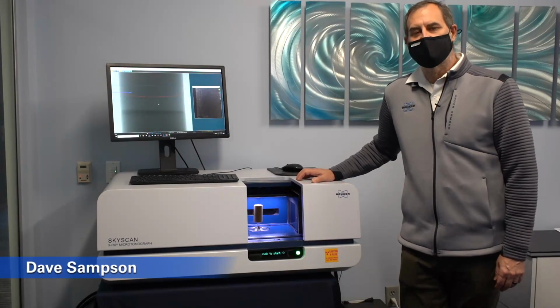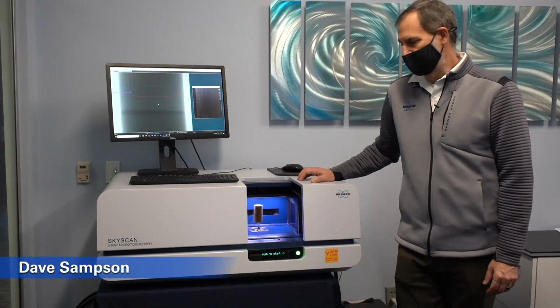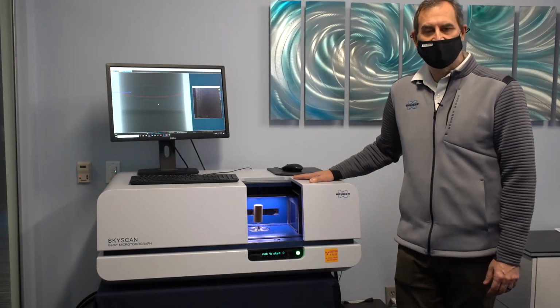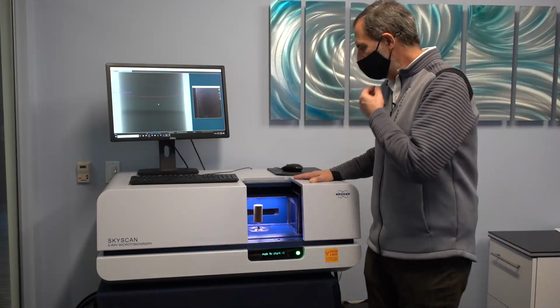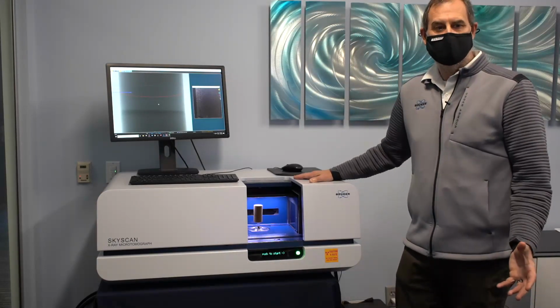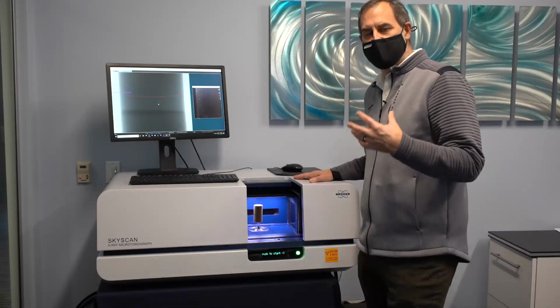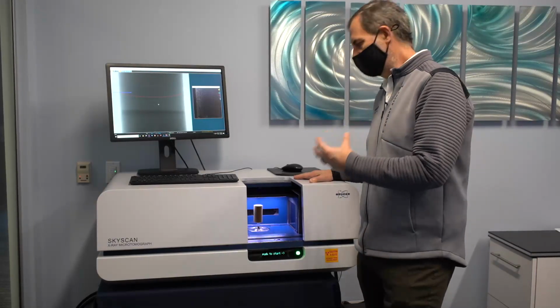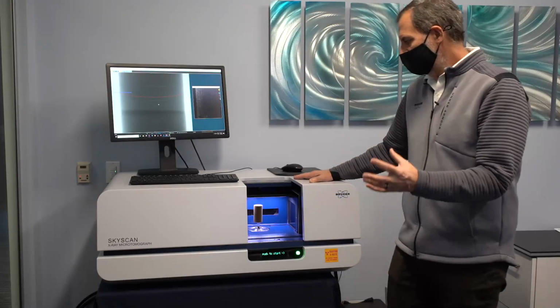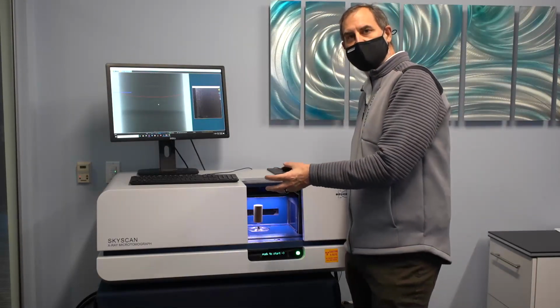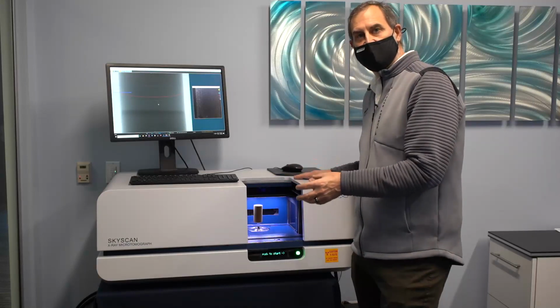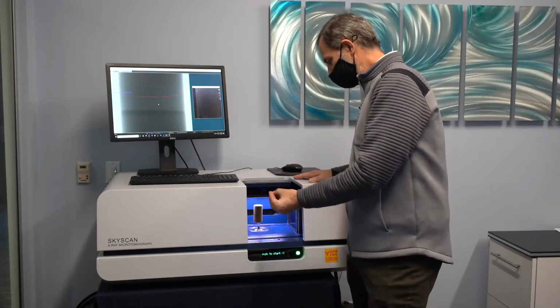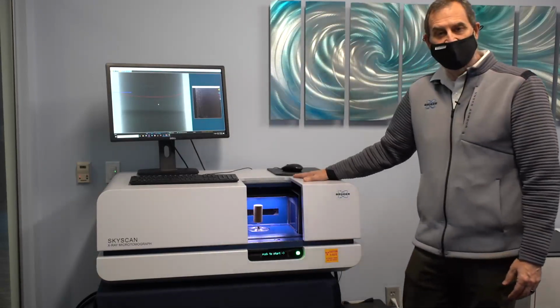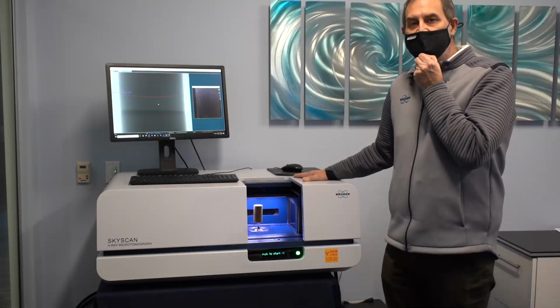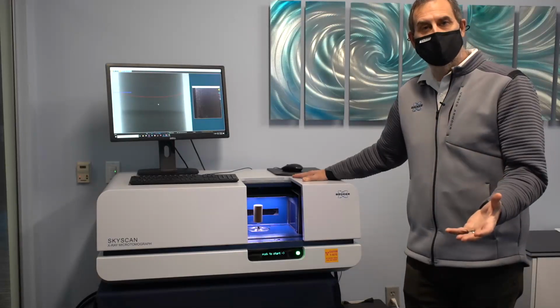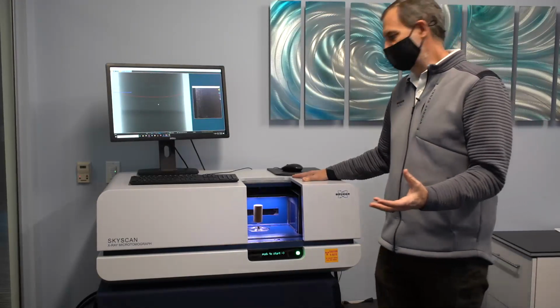Today we're in the Bruker X-ray microscopy lab in Madison, Wisconsin. I'm standing in front of the Bruker Skyscan 1275. The 1275 is our entry-level benchtop system, but we call it a benchtop, but it is a fully functional system with all the bells and whistles. It has a closed X-ray source, meaning it has low cost of ownership and low maintenance. It has a large flat panel detector. Flat panel detectors give you high resolution of a few microns while giving you fast scans.